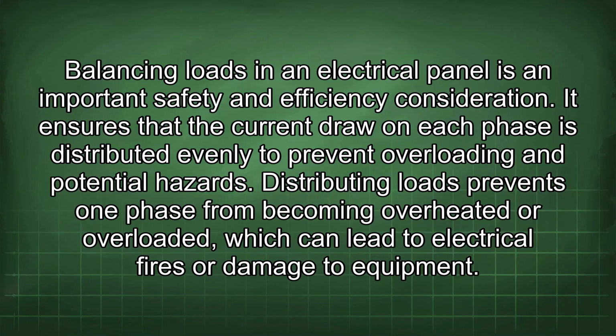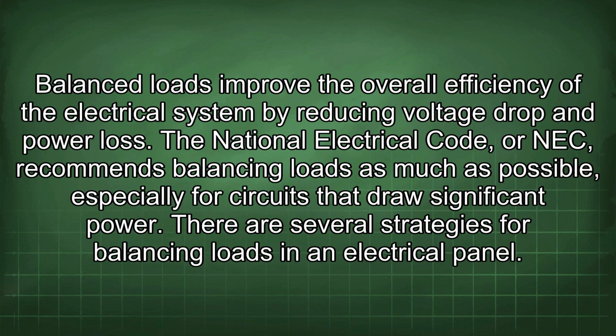Balancing loads in an electrical panel is an important safety and efficiency consideration. It ensures that the current draw on each phase is distributed evenly to prevent overloading and potential hazards. Distributing loads prevents one phase from becoming overheated or overloaded, which can lead to electrical fires or damage to equipment. Balanced loads improve the overall efficiency of the electrical system by reducing voltage drop and power loss.